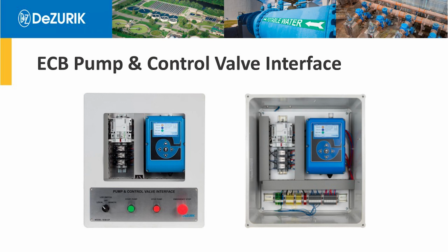The other thing that we've got to be aware of is how do we control all this? When we're using a pump control valve, we've got to stop and start the pump and open and close that power actuated control valve, whether it's controlled via solenoids or an electric motor operator. Generally, you can have a systems integrator do that for you, but there are also valve manufacturers such as DeZURIK who manufacture a pump control panel, and that pump control panel can do the interface for you for single system, single source responsibility.